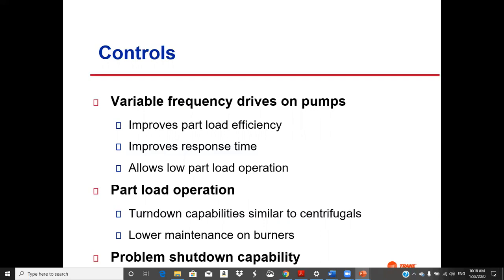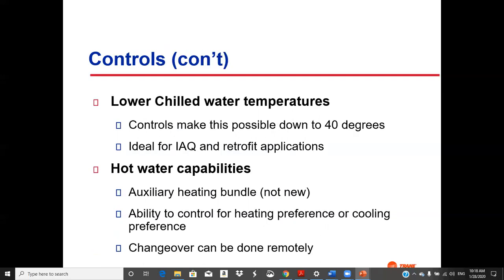Part load operation, turn down capabilities are similar. That's gotten better. Lower maintenance on burners, and shutdown is better. So they've gotten better. Lower chilled water temperatures, it can now go down to 40, which was not possible before. And remember, this direct fired unit can make hot water for space heating as well as chilled water for space cooling. Now you've got to pick one that you're going to design for. If you pick the cooling, then you just get a certain amount of hot water. If you pick the hot water, then you get a certain amount of cooling, so you've got to make sure that fits your applications. And changeover can be done remotely, computer-based.